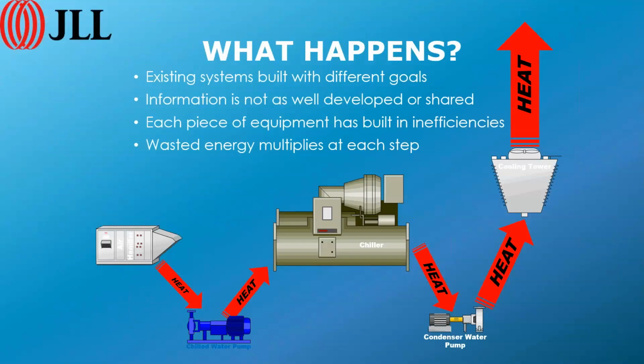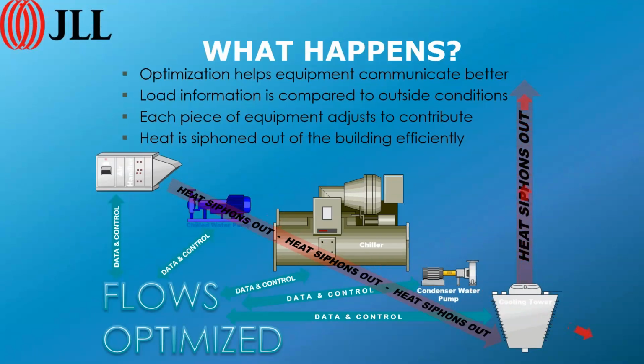So what we want to do is get rid of some system inefficiencies, and this is a function of PID control. PID control is a response generated control algorithm, PI control. Something happens, you make a response. The system tends to over respond, either too much or too little, and then it looks at the error between what its output was and what it was supposed to be, and it starts to make changes in that response. So there's always some overshoot and undershoot in PI loops, and that results in some wasted energy. That wasted energy accumulates as you go through the system. It accumulates at the pump, at the chillers, and it eventually finds its way out through the cooling tower. What we want to do is find a way to siphon that energy out and reduce the amount of overshoot and undershoot in the system. And we're going to do that in some ways that are pretty simple.